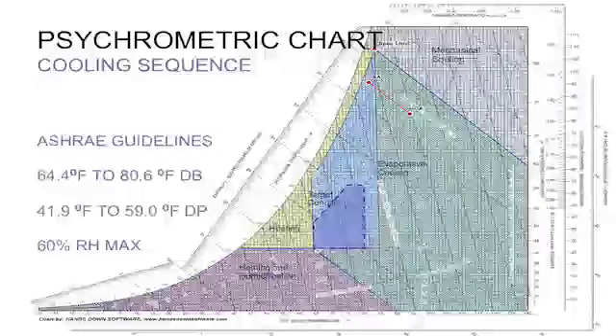Our servers are able to tolerate higher humidity and a higher temperature. So using a psychrometric chart, we identified the regions in which we would be able to support our services. And so this line here was the magic line for us in Forest City, defining that, okay, ASHRAE 50 would indicate that we would have to do some mechanical cooling to peak shave so that our evaporative system would work.